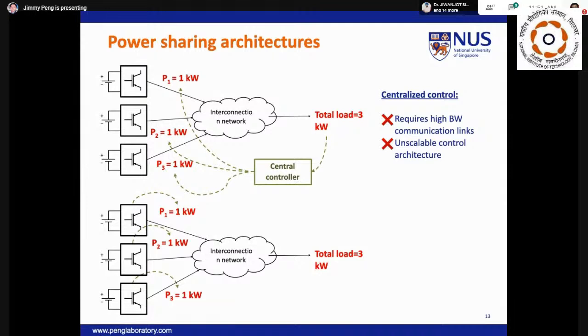On the other hand, the bottom scenario is where decentralized control has been implemented. In this case, each inverter operates in an independent manner where the output power is governed by the feedback signal from local metering equipment. Now, the key benefit of the decentralized philosophy is the investment cost, and it is a critical design factor in commissioning a microgrid. Here, the inverter-based generations do not require an extensive communication network, which lowers the total cost of construction. In addition, it introduces a notion of plug and play, allowing easy integration of new equipment into the microgrid without the need of major overhaul in the microgrid operation.